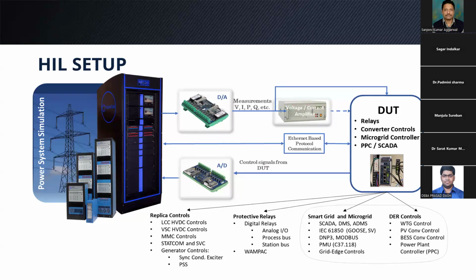And then the relay is a physical device, so it requires physical input. Typically a relay requires three voltages, three currents. Right? VA, VB, VC, IA, IB, IC. So those voltage and current outputs we will take out from the simulator through this card. It's called a digital to analog converter, and that will give you your voltage and currents. If the relay requires voltage or current at a certain power level, then we can have an amplifier in between that will amplify that voltage and current to the level that matches the relay's requirement, and then that will go to your relay.